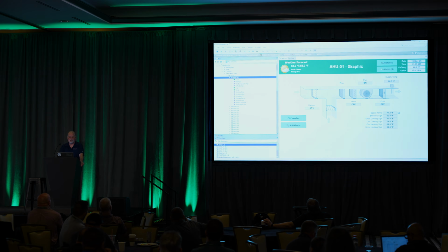So in this case, when I go look at my building nav, I probably don't have time to get into the weeds on that one, so I'm just going to go into the campus nav here. In this case, we'll see that it's going to show me information from both my buildings. And building 200 is not even mapped into the supervisor, right? It's getting to that through building 100. That's that multi-tiered system database design. And these will then show me all the things that the system database knows about, and I'm able to just access these graphics by just double clicking on them, right? And I'm still in the supervisor station up here. I'm connected to my ControlsCon supervisor, okay?